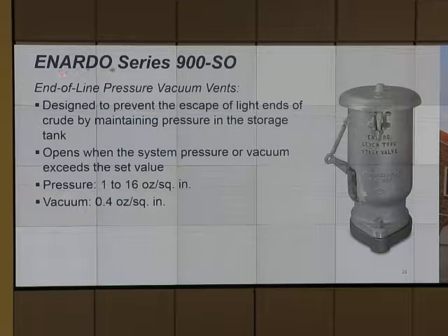Another valve. It's a vent valve that you see on the top. We connect to the vent valve at the very end. So in the worst case, where we cannot capture everything and too much pressure comes and something happens, we want to vent it to the atmosphere. When we vent it, we have to vent far away from any flammable source. So when you go to the tank, we don't smoke.